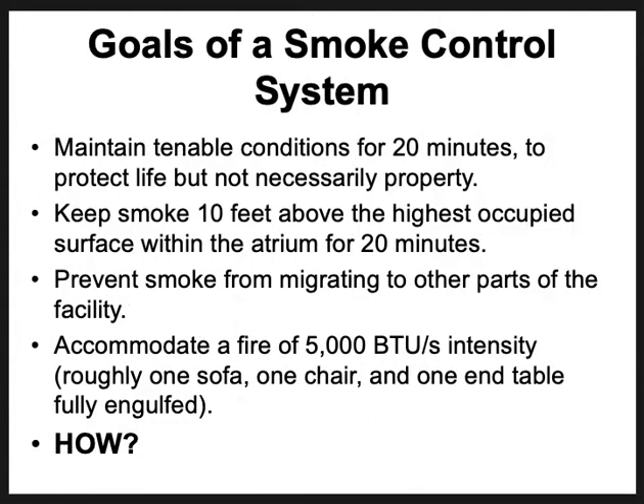So the goal of a smoke control system is to maintain tenable conditions for 20 minutes, to protect life, but not necessarily to protect the property. We're trying to get people out safely, give them more time. So they're going to keep the smoke 10 feet above the highest occupied space by the many usages that we're going to talk about, or the means that we're going to talk about. So they also are going to try and prevent smoke from migrating from one part of the building to another part. The goal is to accommodate a fire of 5,000 BTUs and keep the room from getting engulfed in smoke.